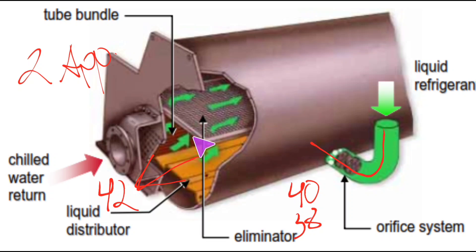At the same time, if you run too low of a GPM, you can actually cause that approach to increase, which may sound kind of weird when you think about it. Okay, well if I'm running the water slower I can cool it easier. And that's true, but that heat exchanger still has to have so much heat input into it. So when you run that water that slow, sure we can cool it down, but we're not going to be able to keep our saturation up, because in the same way, the saturation is going to drop.